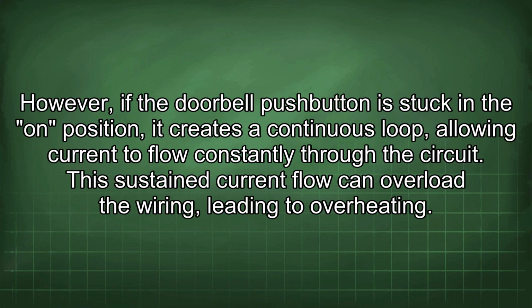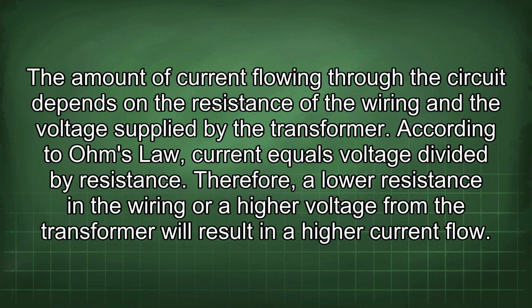However, if the doorbell push button is stuck in the on position, it creates a continuous loop, allowing current to flow constantly through the circuit. This sustained current flow can overload the wiring, leading to overheating. The amount of current flowing through the circuit depends on the resistance of the wiring and the voltage supplied by the transformer. According to Ohm's law, current equals voltage divided by resistance. Therefore, a lower resistance in the wiring or a higher voltage from the transformer will result in a higher current flow.